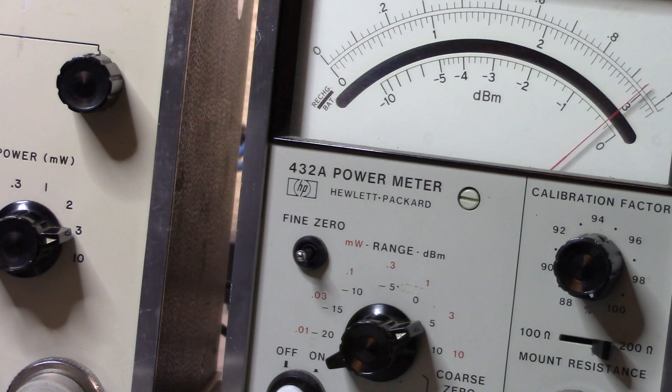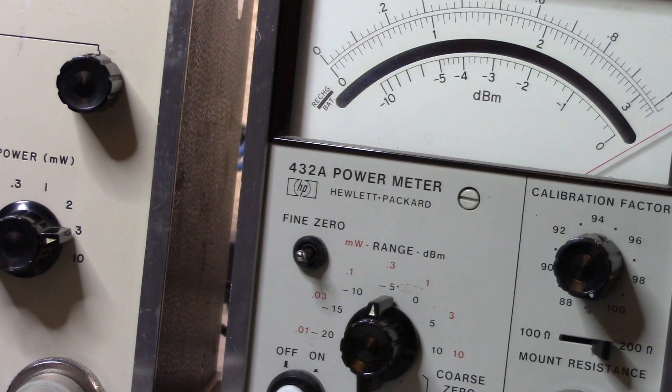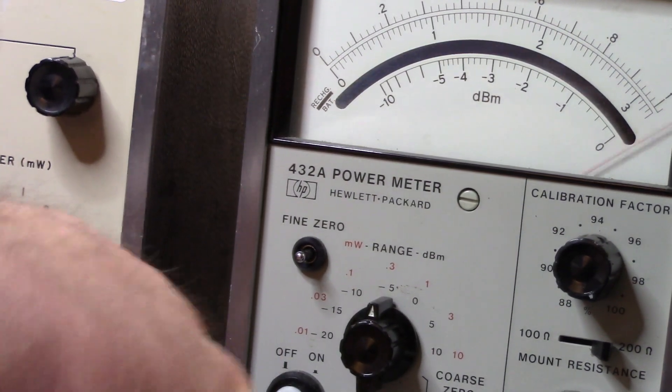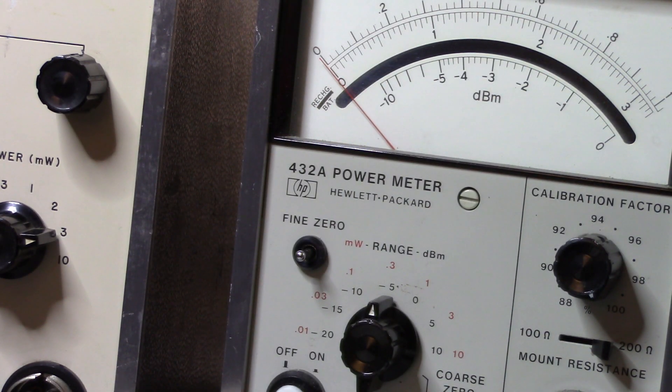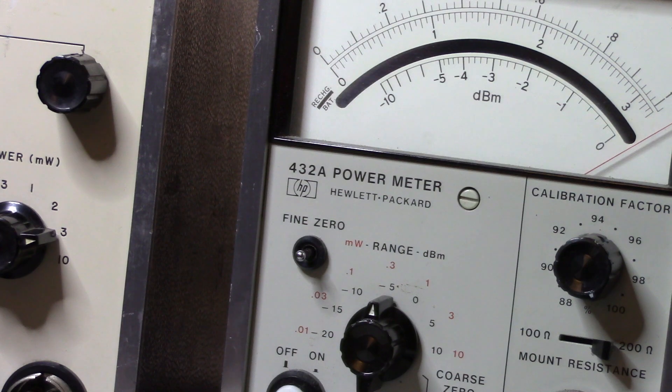Find zero, set the 432 to 0.3 milliwatts, and then I'm supposed to connect the thermistor mount. Let's disconnect this guy here. This is my thermistor mount that I've just gotten back from Keysight. This one's an H76, so the actual frequency range on this only goes up to one gigahertz.